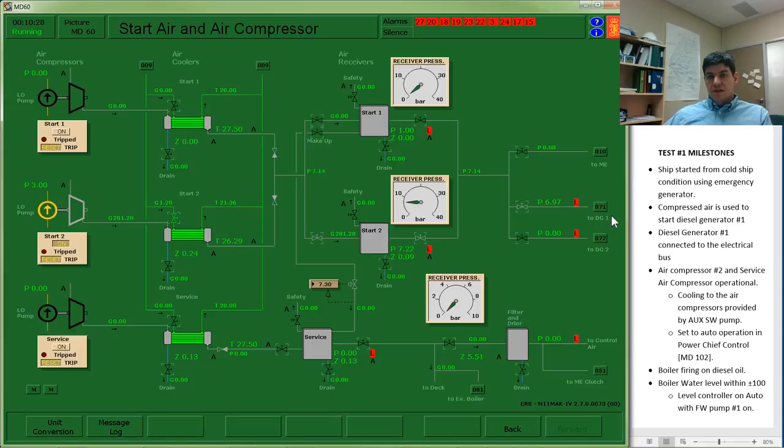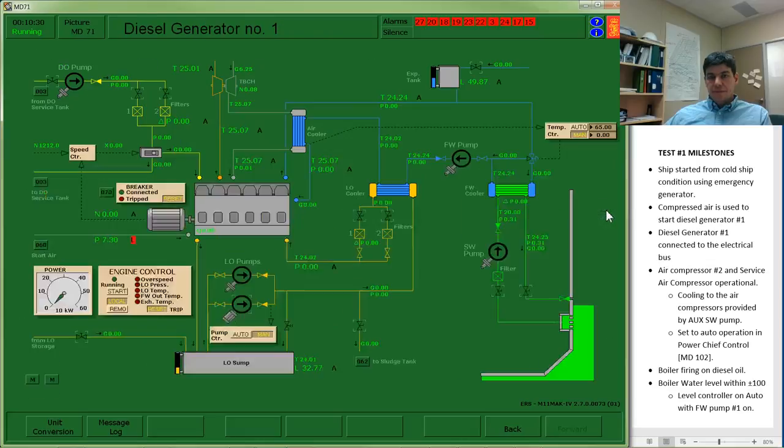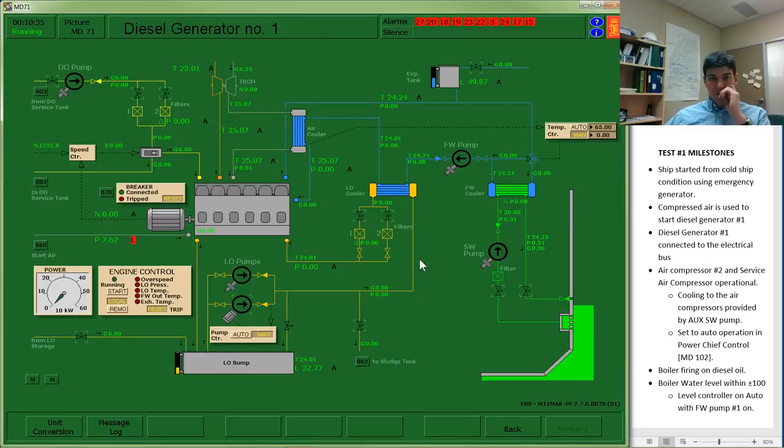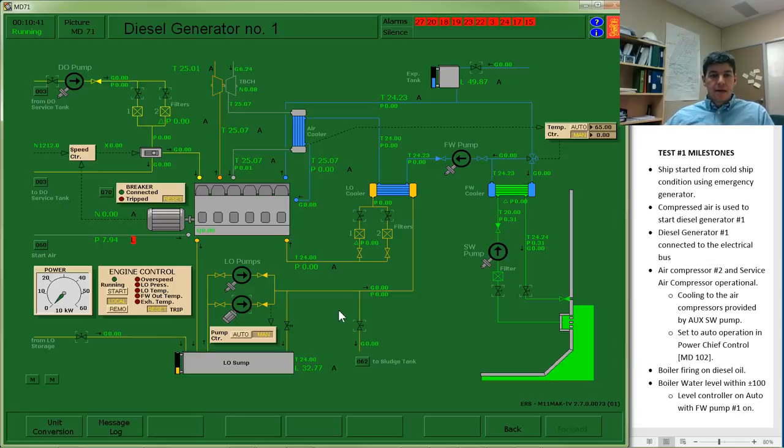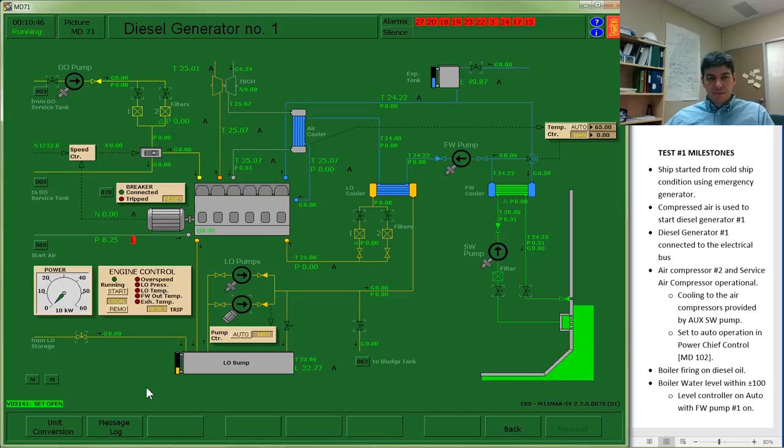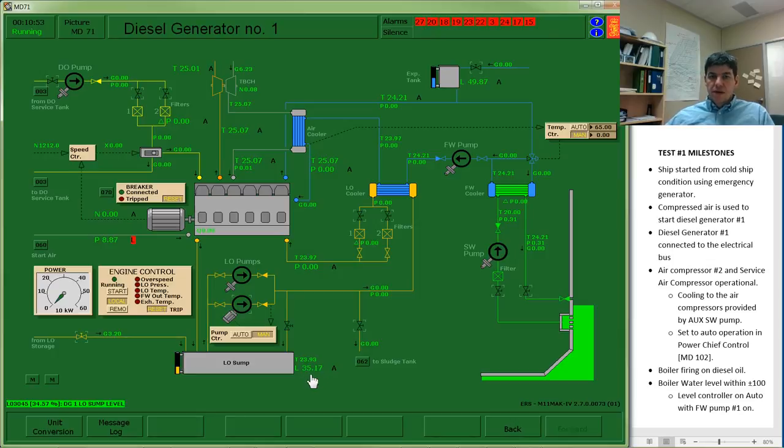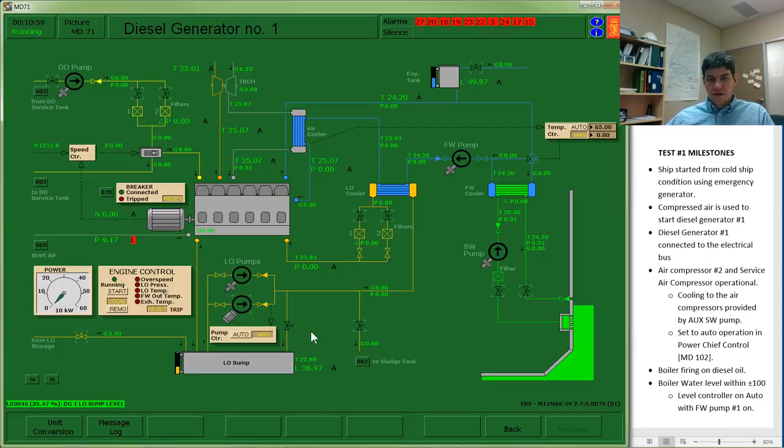So off to diesel generator number 1. Diesel generator number 1 has a number of systems. I'm going to start with the lube oil system. So down here at the bottom, I have my lube oil system. If my lube oil level is low, I can add in lube oil. I may want to target about 50% as my lube oil level. So if it is a little low, we could add some. If it's high, we can remove some oil using this valve and our pump.